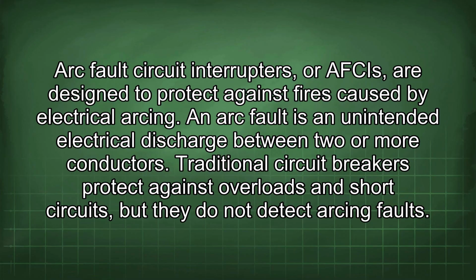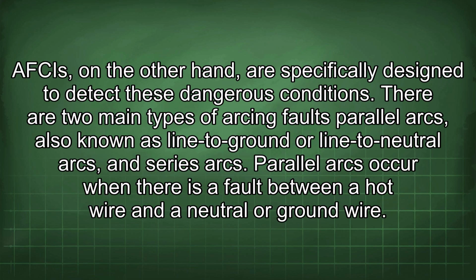Arc fault circuit interrupters, or AFCIs, are designed to protect against fires caused by electrical arcing. An arc fault is an unintended electrical discharge between two or more conductors. Traditional circuit breakers protect against overloads and short circuits, but they do not detect arcing faults. AFCIs, on the other hand, are specifically designed to detect these dangerous conditions.